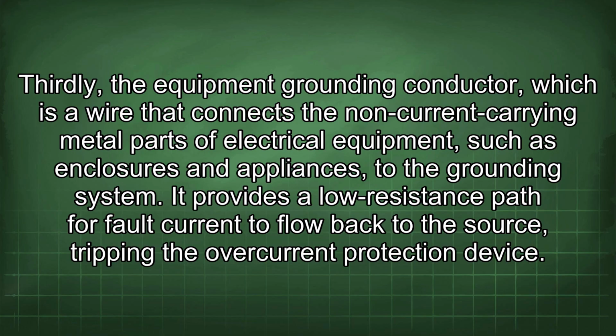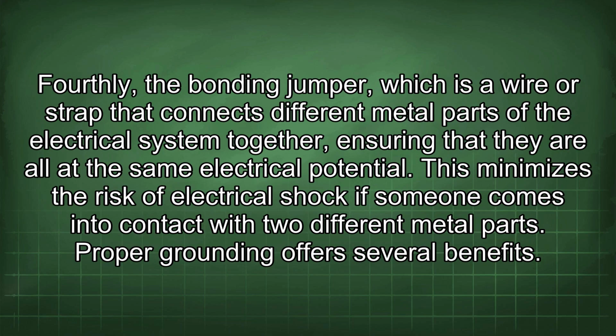Thirdly, the equipment grounding conductor, which is a wire that connects the non-current carrying metal parts of electrical equipment, such as enclosures and appliances, to the grounding system. It provides a low-resistance path for fault current to flow back to the source, tripping the overcurrent protection device. Fourthly, the bonding jumper, which is a wire or strap that connects different metal parts of the electrical system together, ensuring that they are all at the same electrical potential. This minimizes the risk of electrical shock if someone comes into contact with two different metal parts.